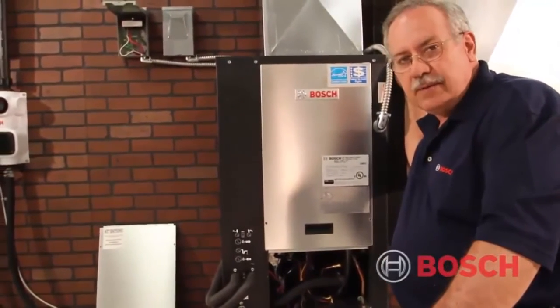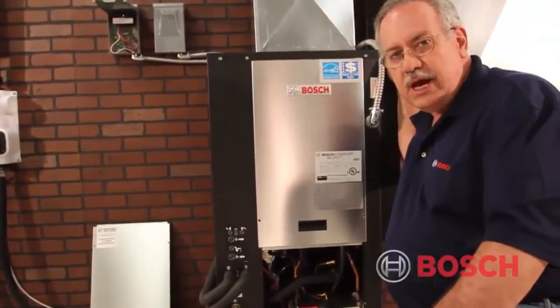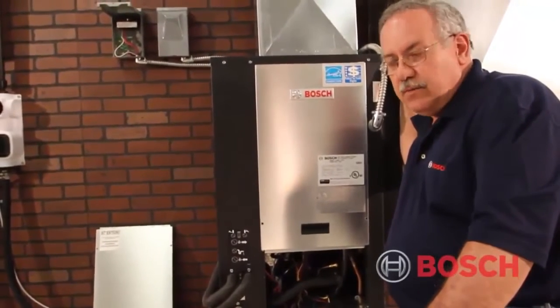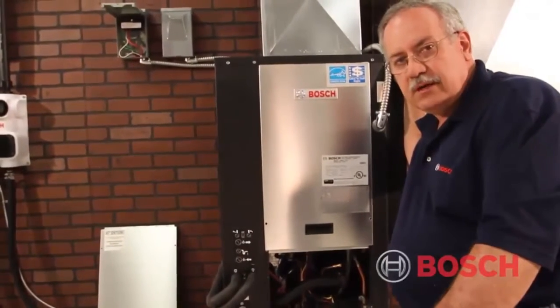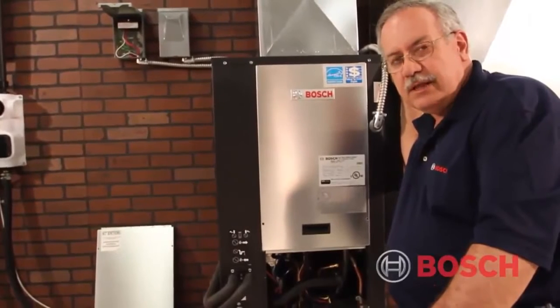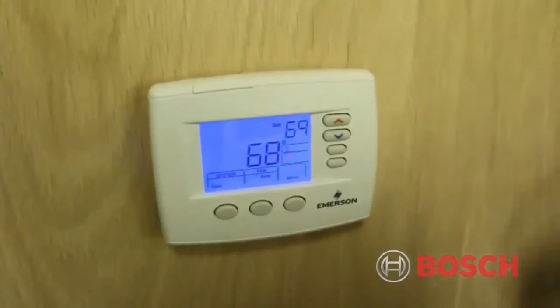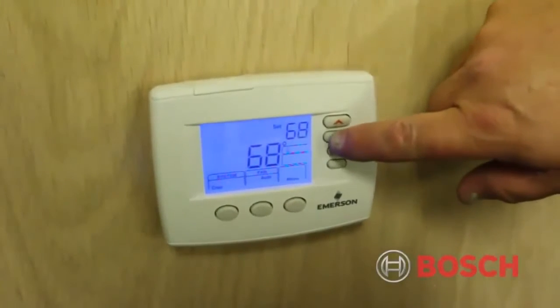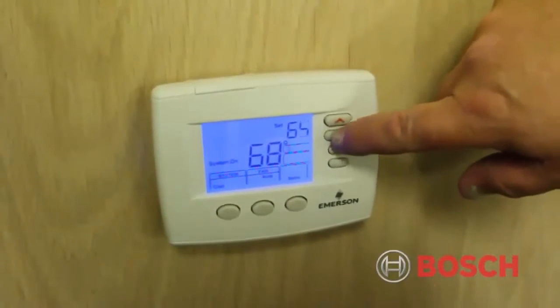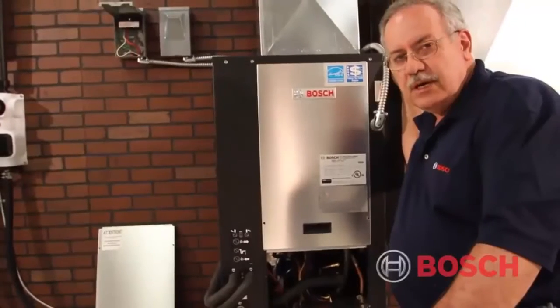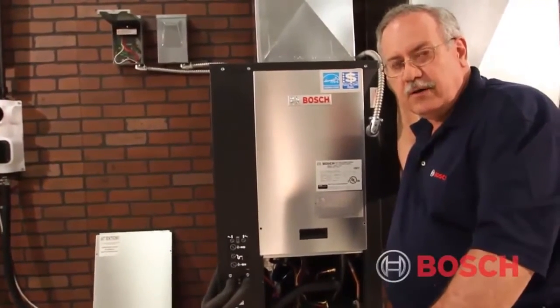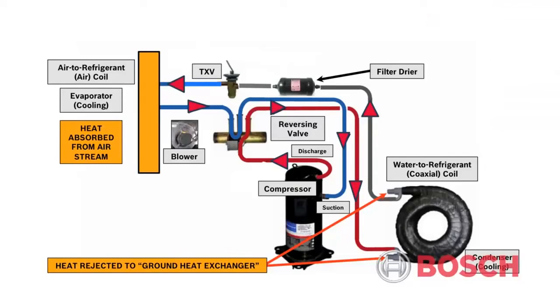We'll energize the unit. Now we always want to check a geothermal heat pump after it's been running for approximately 10 to 15 minutes. The first thing that I would always do is energize it in the cooling cycle and let it run for a few minutes, even if I'm checking it in the winter. The reason for this is because in the refrigeration processes in the cooling cycle, the refrigerant that may have air and non-condensables in it hits the molecular sieve drier, the bidirectional drier, in the refrigerant circuit first, helping remove any non-condensables that might be in it.